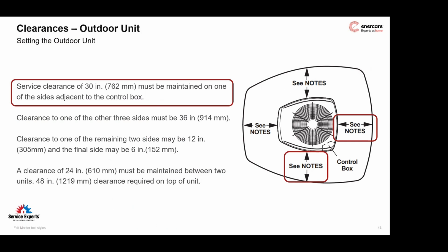Again, a couple of side notes, nothing really crazy. Clearances for the outdoor unit. They want service clearance on either one of the sides adjacent to the control box for the service technicians that are going out to work on these things. Again, I highlight the one on the right side there. You can see that's highlighted now. I would pick that because typically the piping line set comes off the house on this side over here. I would rather have a shorter space up against the house if I'm installing that.